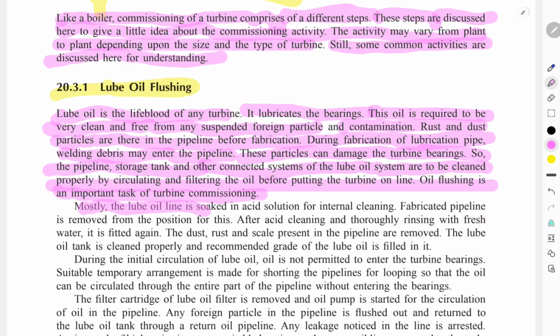Mostly the lube oil line is soaked in acid solution for internal cleaning of the fabricated pipeline, removed from all positions. After this acid cleaning, rinse thoroughly with fresh water, to remove the dust, rust, and scale present in the pipeline. Clean the lube oil tank properly, and fill the recommended grade of lube oil. During the initial circulation, the lube oil is not permitted to enter the turbine bearing. A suitable temporary arrangement is made, shorting the pipelines into a loop, so that the oil can be circulated throughout the entire pipeline without entering the bearing.